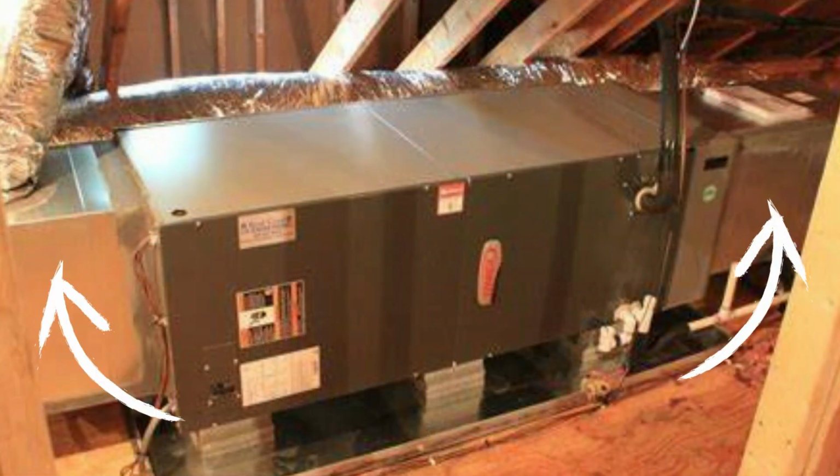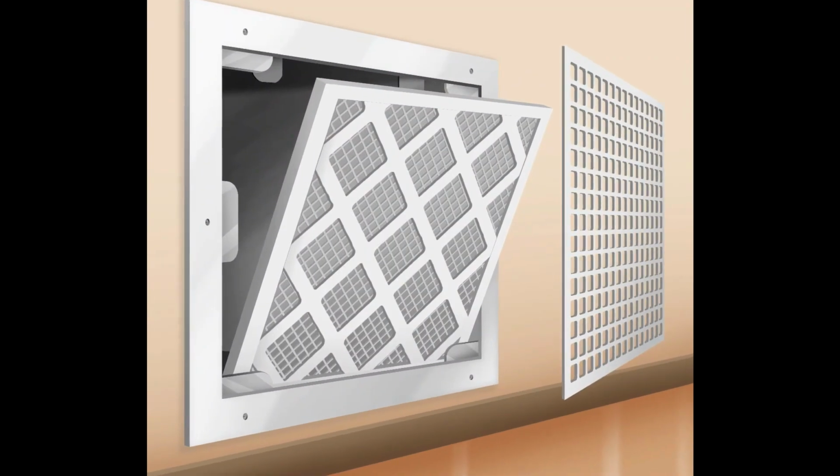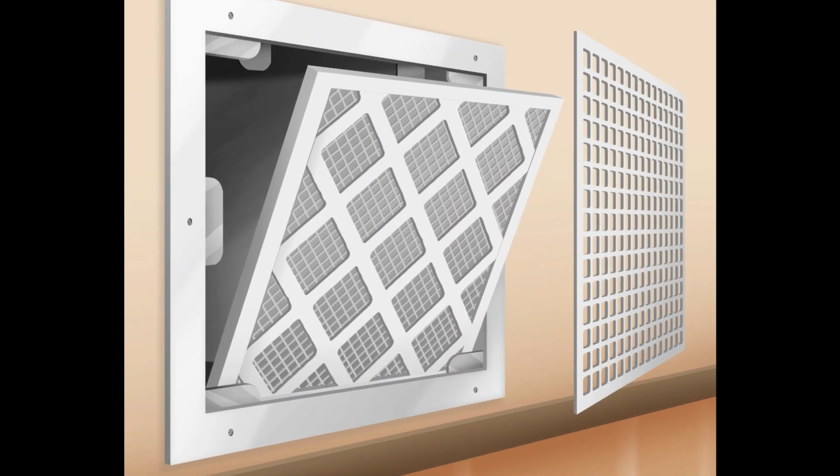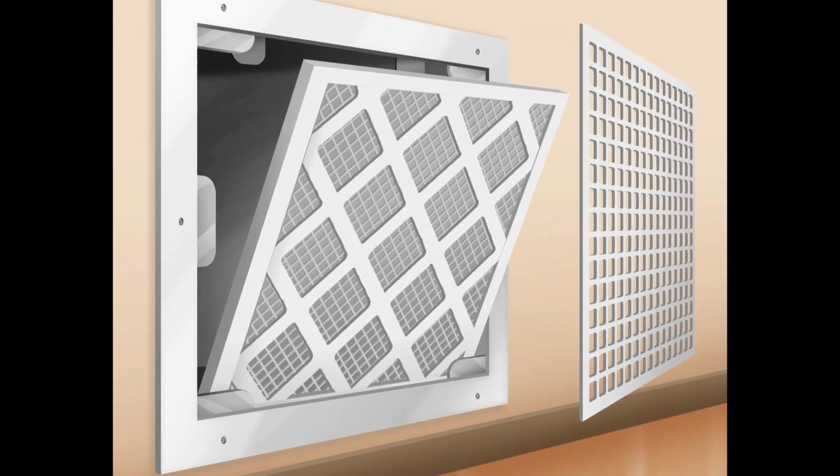Now the first two temperatures we're going to take is called delta T in the trade. This is the temperature difference of our indoor unit, the air coming in and the air leaving. Usually we take these temperatures right in the ductwork itself as close to the unit as possible, but for practical purposes you can do it at your return and supply grills right in the living area. So the first measurement we're going to take is at the return grill. This is where the air from the home enters into the duct system and starts heading towards the indoor unit. For a lot of people this is the same place you change your filter.